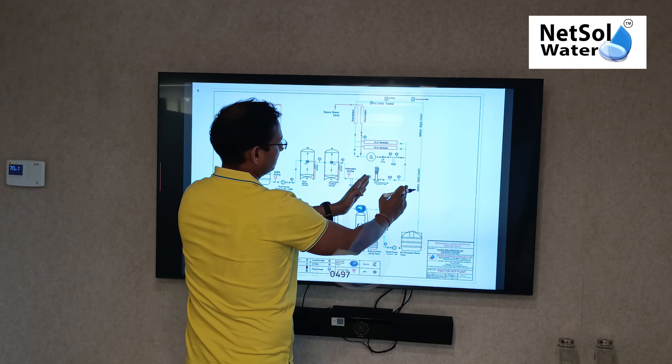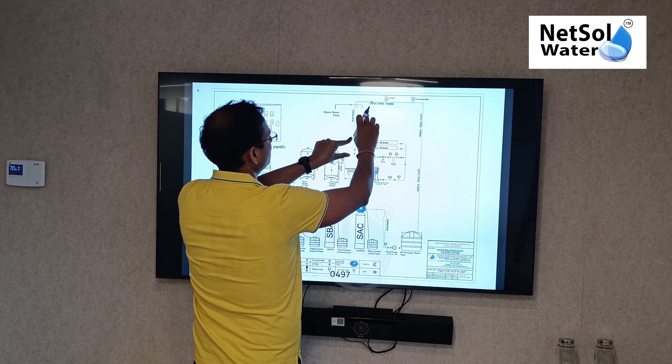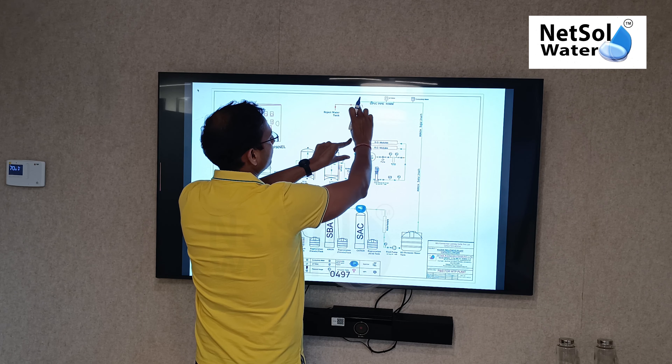The plant has three stages. First, it has an RO. Then we have a DM plant. Then it has a mixed bed plant. Now, in the RO, there is a dual-media filter, then an activated carbon filter, then a micron filter. Then, with a high pressure pump, this water is passed through the membrane. You can see how much permeate water is coming and how much reject water is coming, with a TDS meter and conductivity meter to show the pH and conductivity.